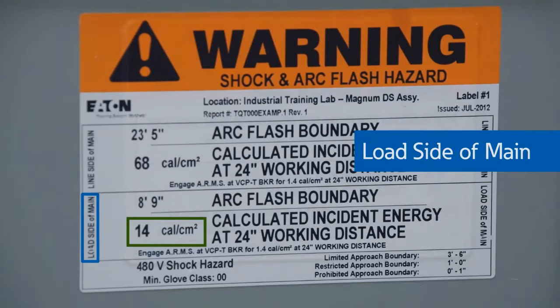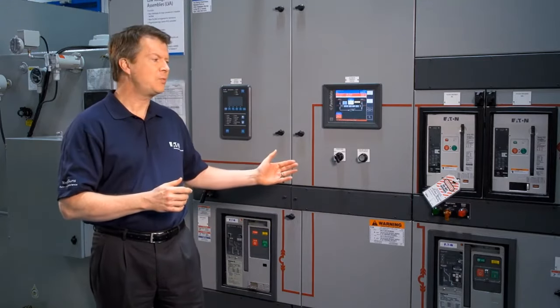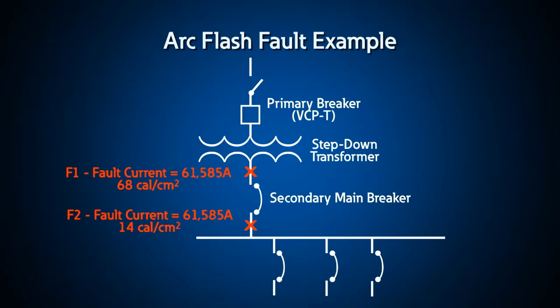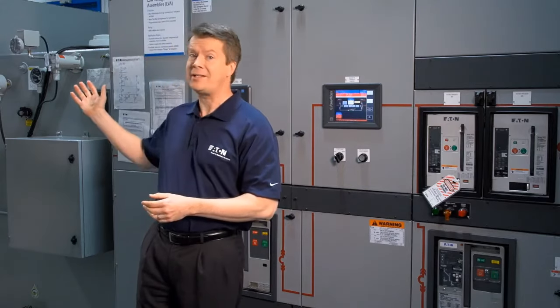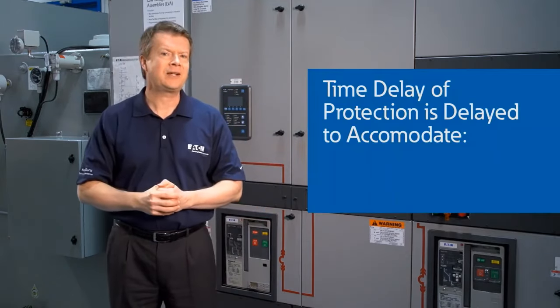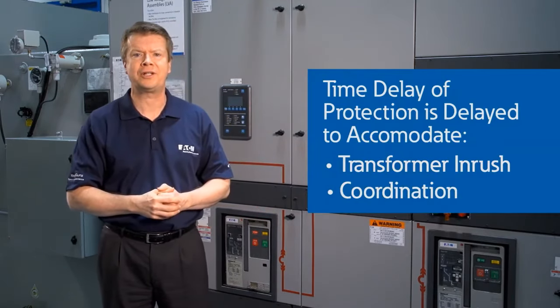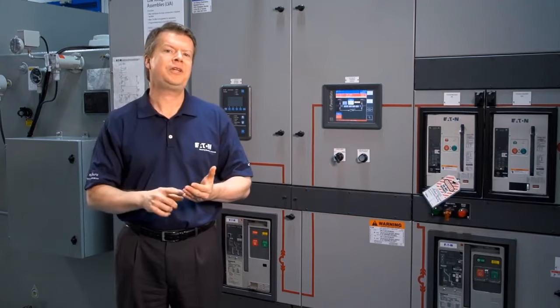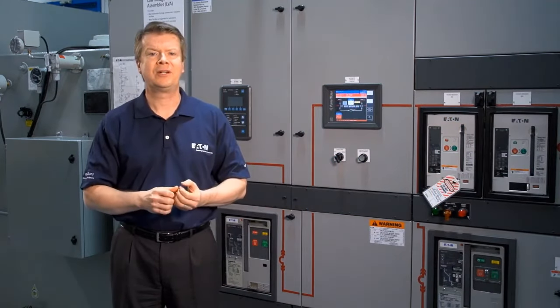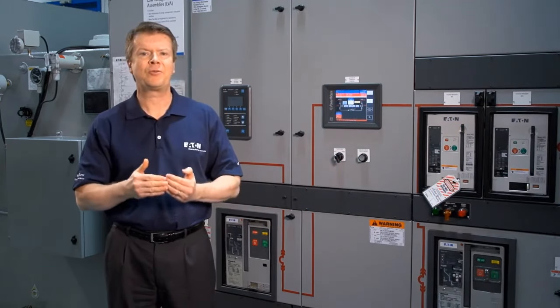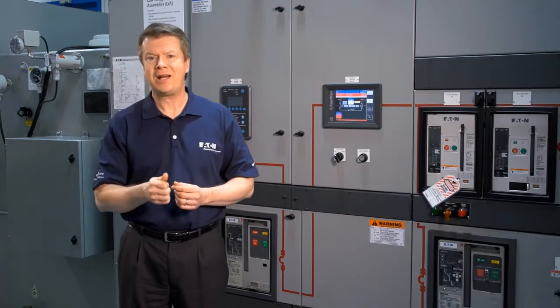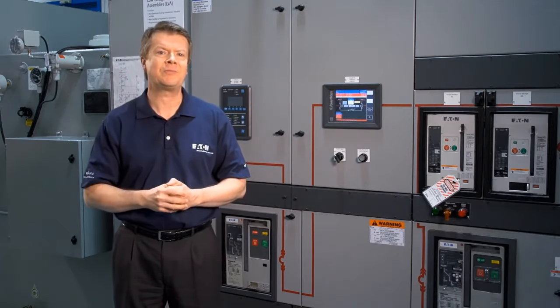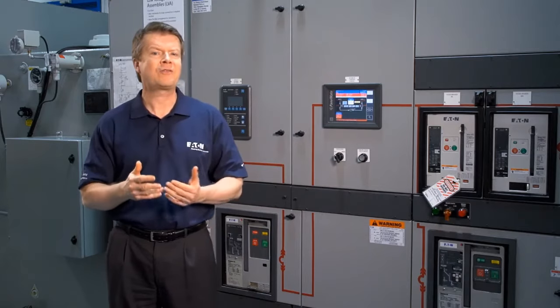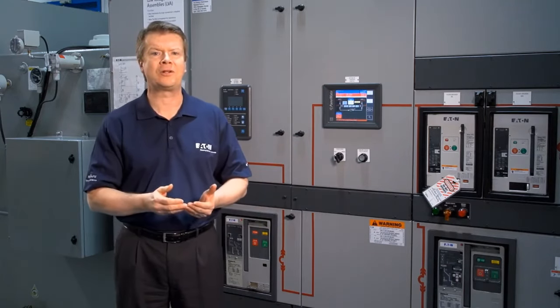For a fault on the secondary, this breaker can trip quickly. For a fault just on the other side of this breaker, even though the fault current is the same, the energy is much higher because the clearing time of the nearest upstream device is intentionally delayed to compensate for transformer inrush and coordination. So how could we create a selectively coordinated system that compensates for the expected transformer inrush, but at the same time clears a fault on the line side of this main breaker quickly enough so that the arc flash energy levels are substantially lowered?